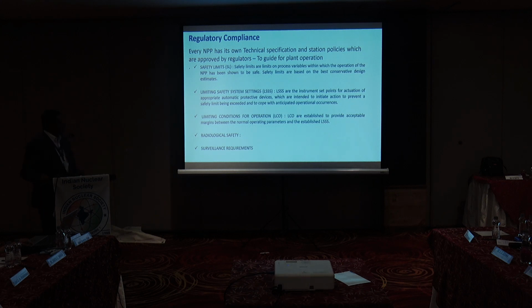Then comes the limiting safety system setting. LSS are the instrument set points for actuation of the appropriate automatic protection device. Based on the safety system, considering the conservative approach, you provide the instrumentation. Like for a pressure vessel designed for this much pressure, you give a safety margin and put the safety limit slightly below it. And the limiting safety system will actuate devices which ensure that the reactor pressure boundary doesn't exceed the safety limits in any conditions.